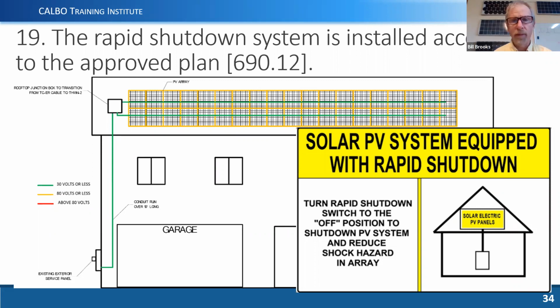Rapid shutdown. Everyone loves to talk about rapid shutdown. Unfortunately, I'm the one that coined the phrase. Although it's maybe not super descriptive, most people know what we're talking about. Rapid shutdown is designed for firefighter safety in the event that they would have to get on the roof and work around this equipment. It enables the equipment to be put in a lower hazard condition. And it's going to have this sign that you see in the bottom right corner: solar PV system equipped with rapid shutdown. Turn rapid shutdown switch to the off position to shut down PV system and reduce shock hazard in array. And so that's the sign that the code asks to see.